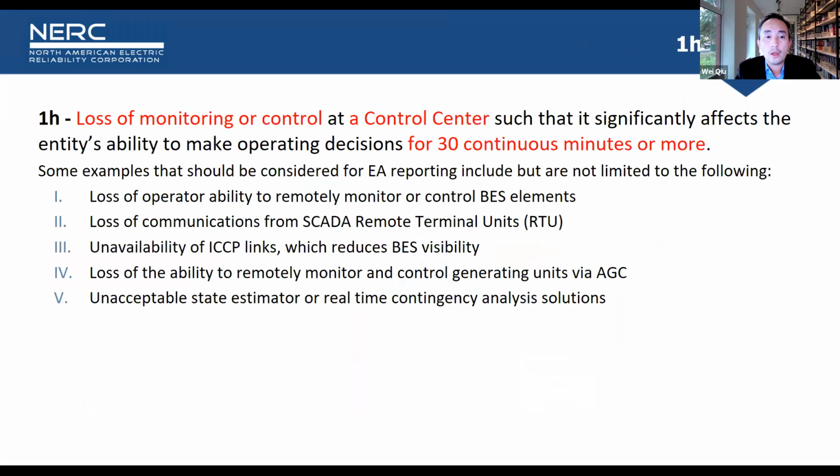As shown before, for the EMS event we also have a definition, because not all EMS issues qualify as an event. Highlighted here, first you need the loss of monitoring or control capability at the Control Center. The Control Center has two uppercase Cs, which means the control center is staffed, with an engineer on site. A remote, unmanned control center is not counted. Also, the event needs to last at least 30 minutes. If you solve the issue within 30 minutes, you don't have to report it to us, but we're happy to learn, because near-miss events are also something we want to study.